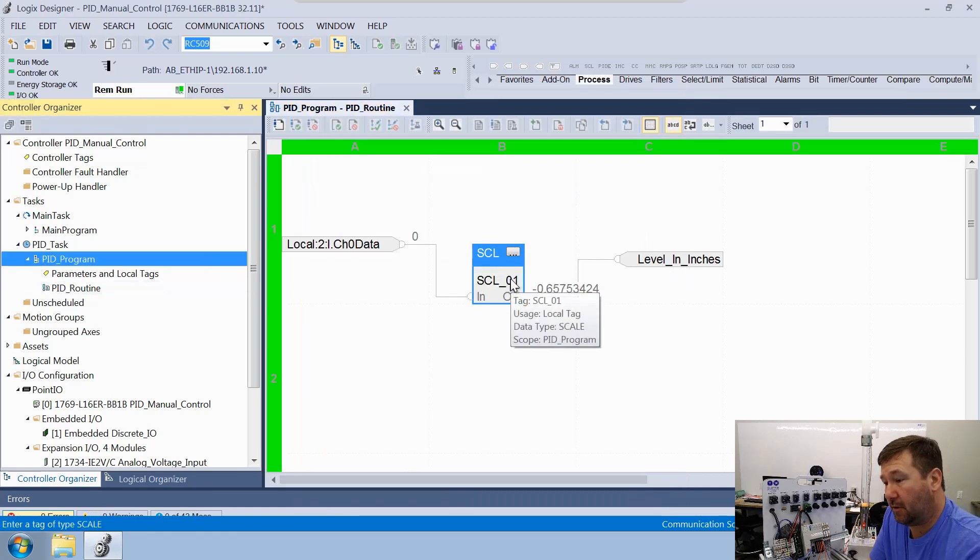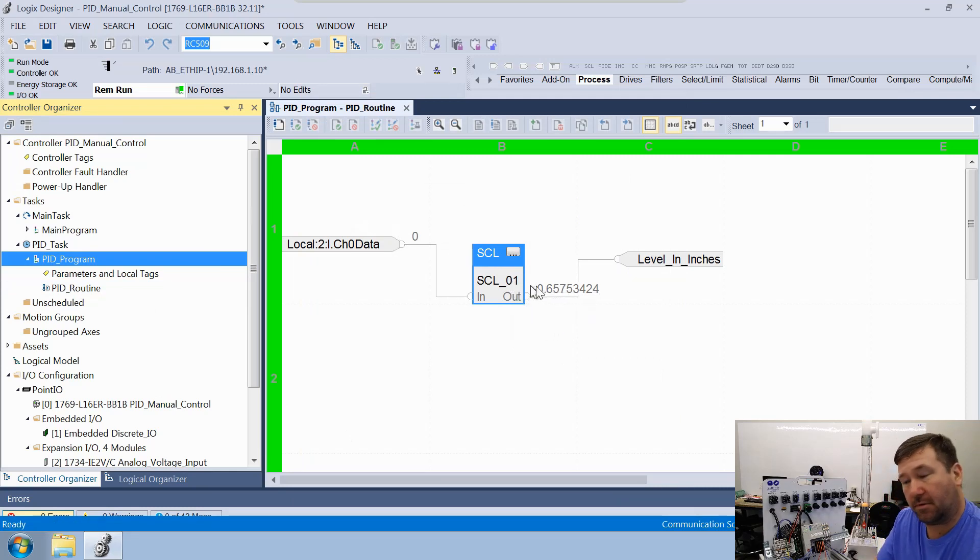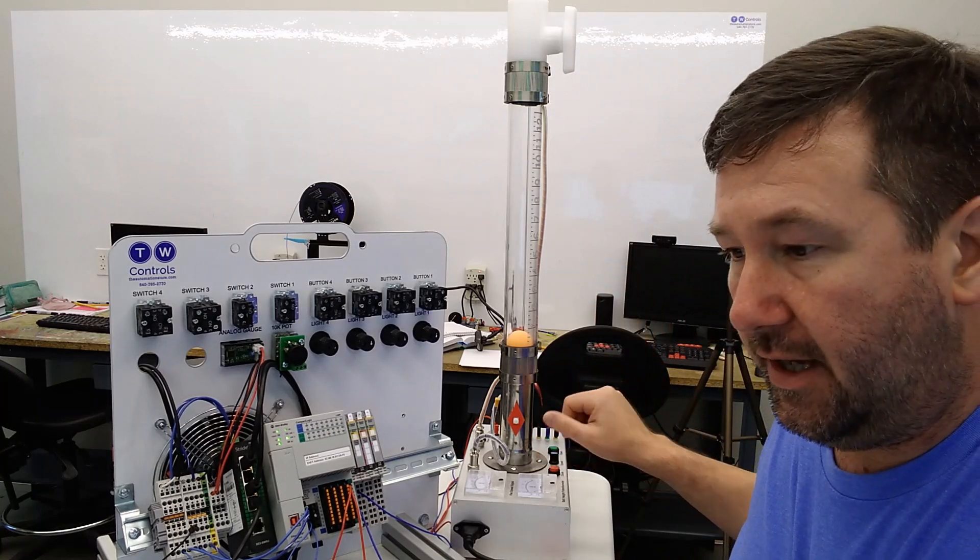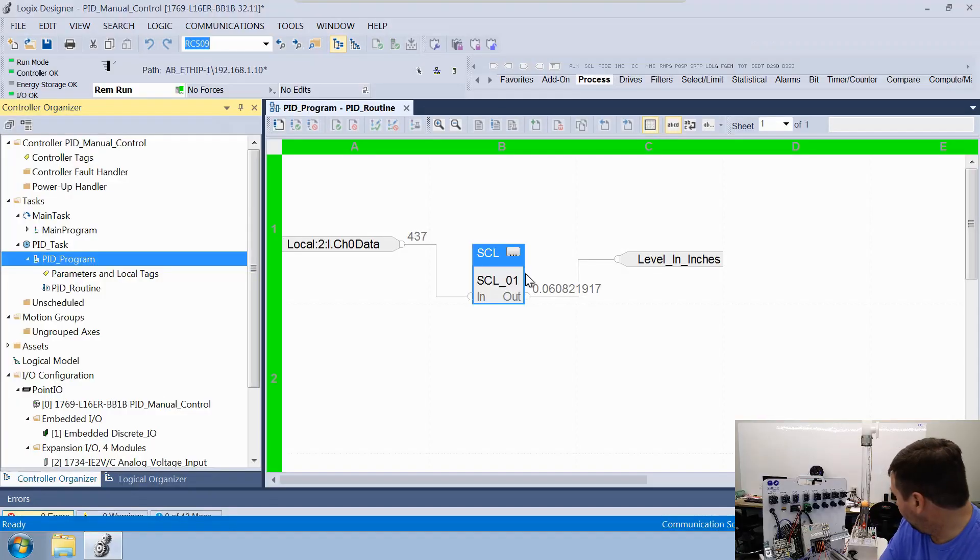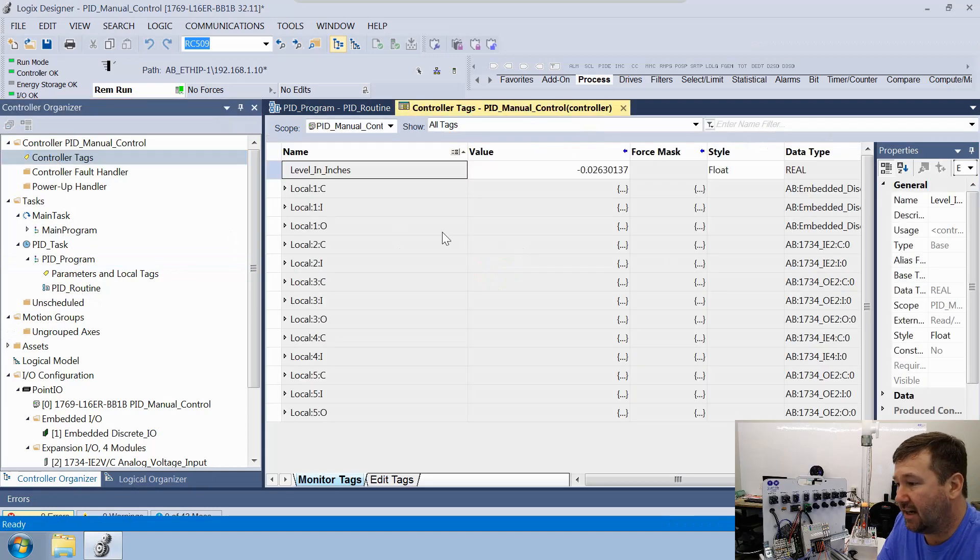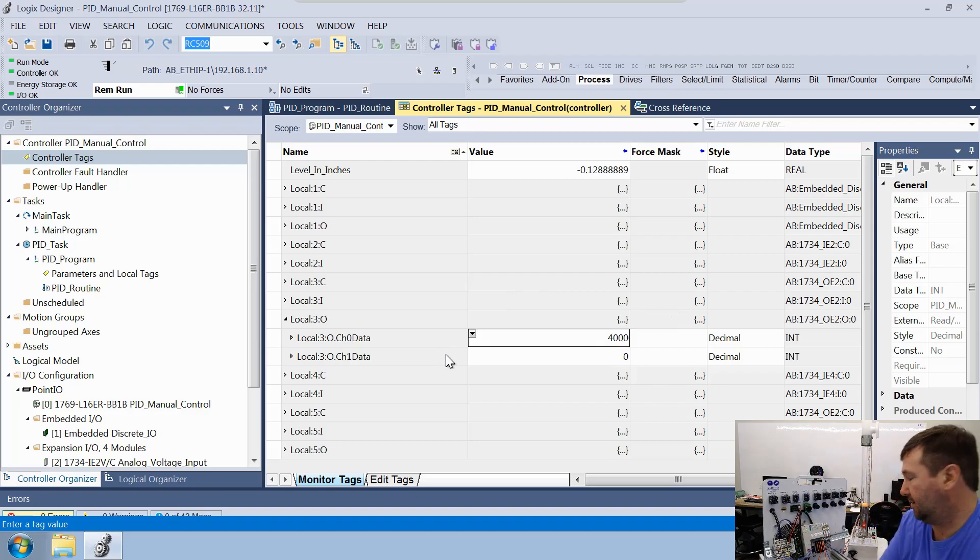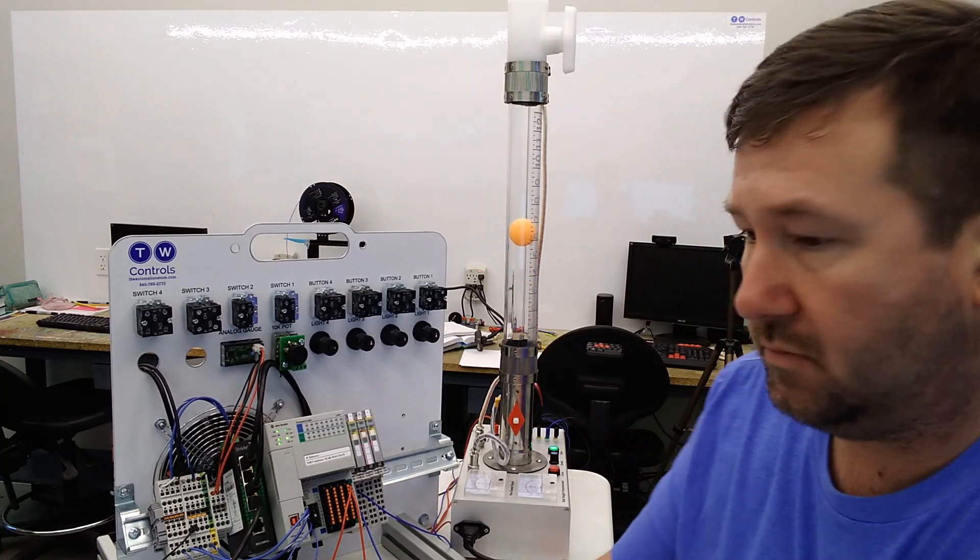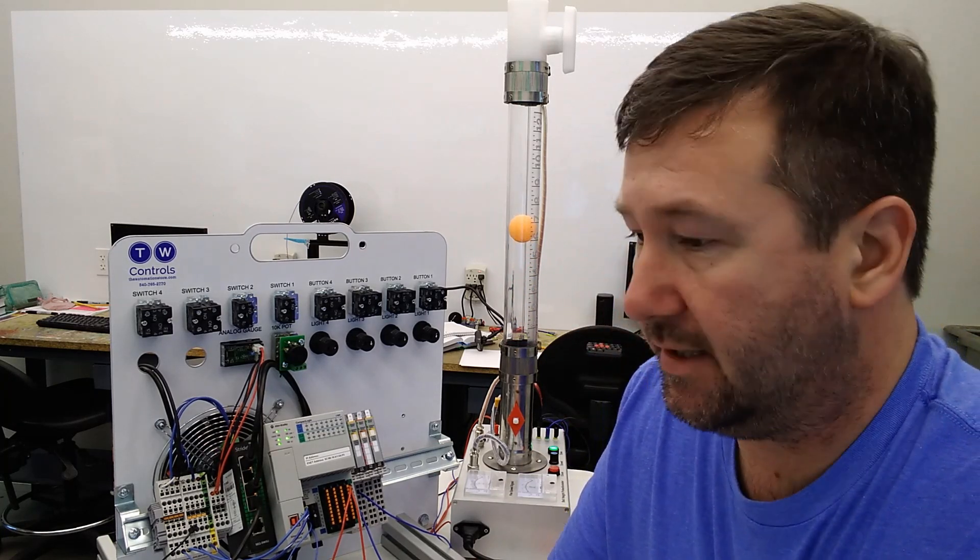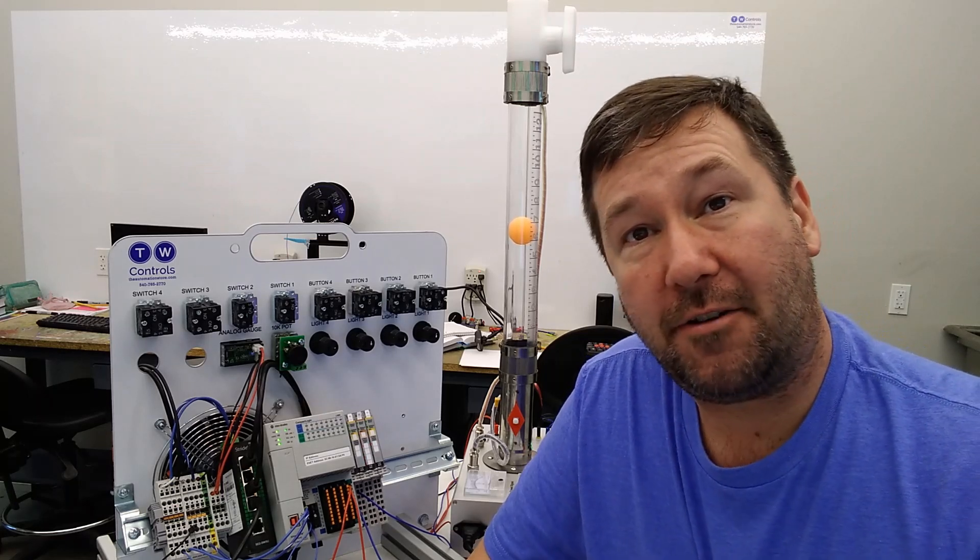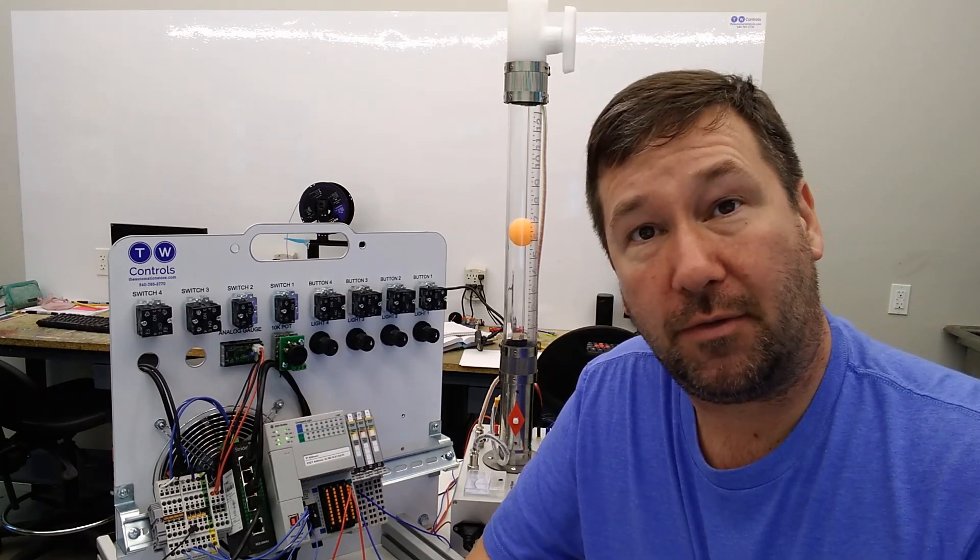Now let's go ahead and download this program. We're actually showing zero right now on channel one, so we're showing a negative. That's because we have the power off. Let's turn the power on. It is bouncing a little bit. Let's go back to our controller tags now and let's just throw 4000 at it. Looks like we're about seven inches. So our scaling is fairly accurate, accurate enough that we can definitely do on-off control.